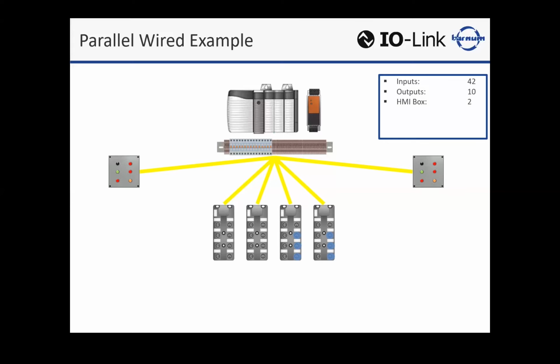Analog. So analog, obviously, with processes becoming more rigidly controlled and traceability and quality being such a featured point of product, analog is becoming more popular. And in the typical parallel wiring example, we would take analog and hardwire that directly back to the panel to a PLC. It's like an analog input card, perhaps, or output card. So let's add one of those as well.